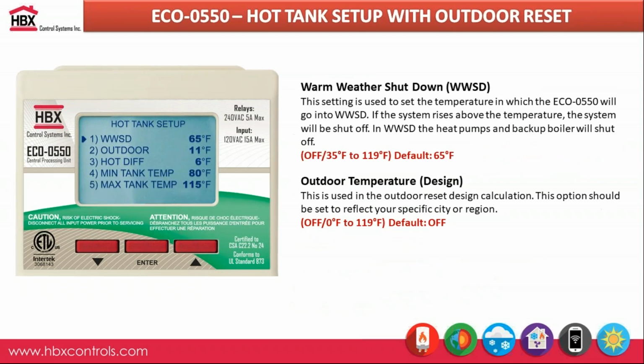And then you can implement your warm weather shutdown as well for heating. And again, you can do cold weather shutdown in terms of your cold tank setup on there. If you are doing outdoor reset, what really is different in terms of setup is that you would put your recommended outdoor temperature for your location. This is the temperature where you would put in the coldest day that it's ever going to get in this location.